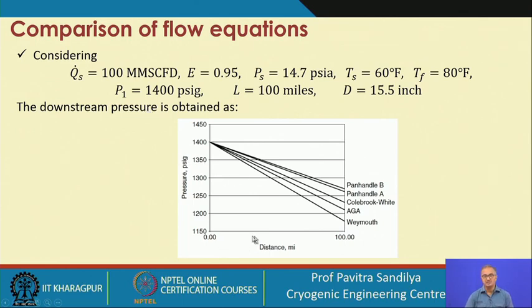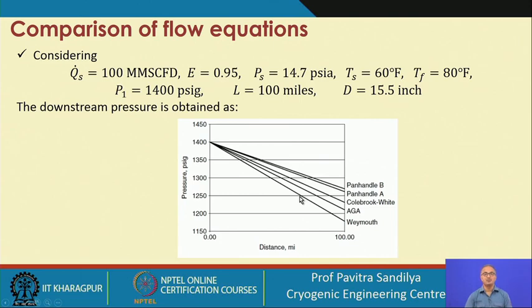You can see how the downstream pressure changes with distance over 0 to 100 miles. Initially, all equations start from the same value, and for small distances the predictions are almost similar. As the distance increases, differences appear in the downstream pressure values — that is, the frictional loss is calculated differently by the different expressions. In this case, Panhandle B gives the highest downstream pressure and Weymouth gives the lowest.